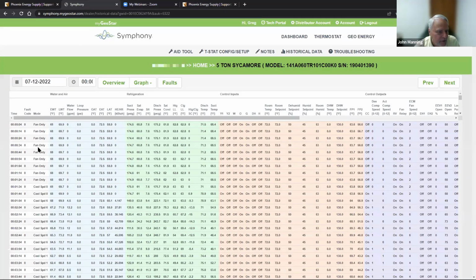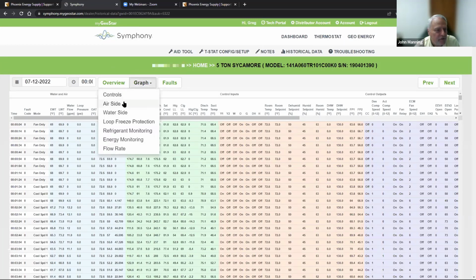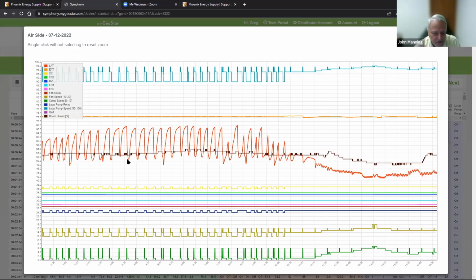We can go to the 12th. And it downloads the complete 24-hour history in 10-second intervals. And one of my favorite graphs is the air side graph. So we can see the speed of the compressor is the lower chart. And during the night, the cooler hours, it was cycling on speed 1. And you see these spikes up to speed 6. And by design, every time the unit starts, it goes to speed 6 to make better oil circulation within the compressor itself. And even once it gets up and running, it'll start on speed 6, but every 30 minutes of runtime, it'll also bump up to speed 6. So you'll see these little spikes.